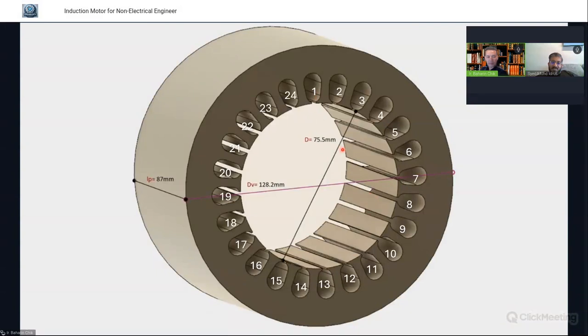Because the rotor may touch this stator core. I see. Meaning the reason why this core is broken is maybe because the bearing gives way, and then the rotor will hit the stator core inside, and then it breaks. So once that situation occurs, you cannot run the motor at all. So it looks like vibration will be high if there are signs of that. Yeah, vibration comes first. Vibration comes first because maybe the bearing gives way, then it causes vibration, and then if we don't look at it, that vibration causes the rotor to slam into the stator core, and then it breaks.